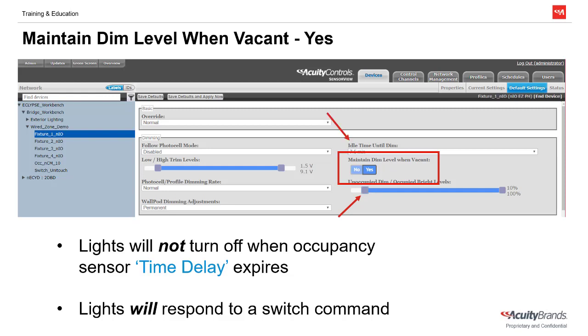The unoccupied dim level is also the same light level the lights will dim to after the idle time until dim has expired. If this value is less than the occupancy sensor's time delay, the lights will dim before the occupancy sensor expires. If it is greater, the lights will dim when the occupancy sensor's time delay expires. In a real-life application, the unoccupied dim level should be changed to the light output required to achieve a specified light level dictated by regional code or by the sequence of operation as noted in the electrical plans.